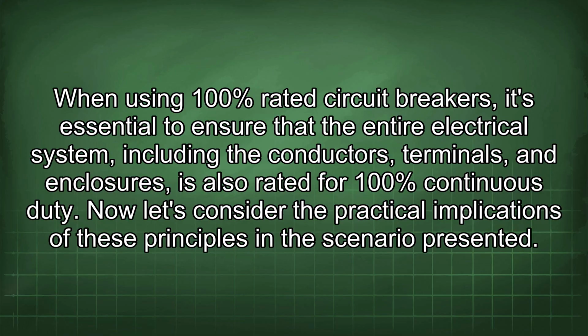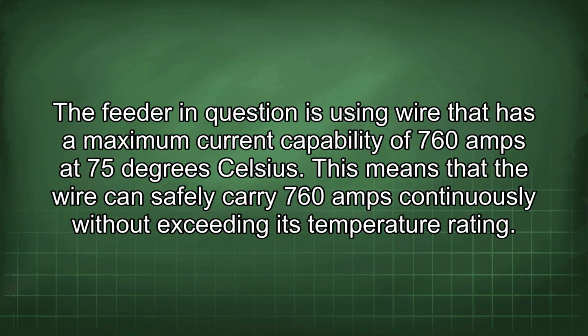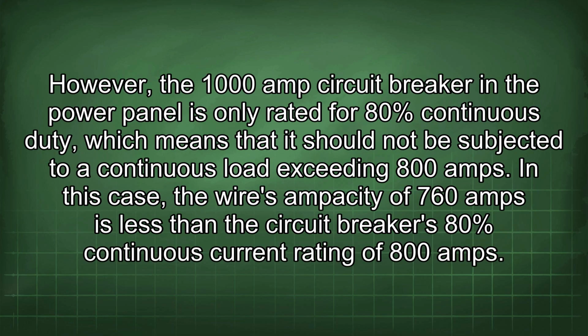Now let's consider the practical implications of these principles in the scenario presented. The feeder in question is using wire that has a maximum current capability of 760 amps at 75 degrees Celsius. This means that the wire can safely carry 760 amps continuously without exceeding its temperature rating. However, the 1000 amp circuit breaker in the power panel is only rated for 80% continuous duty, which means that it should not be subjected to a continuous load exceeding 800 amps.